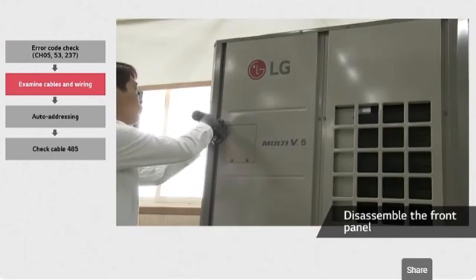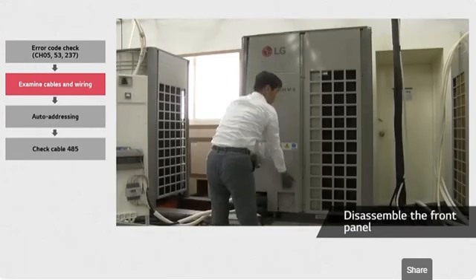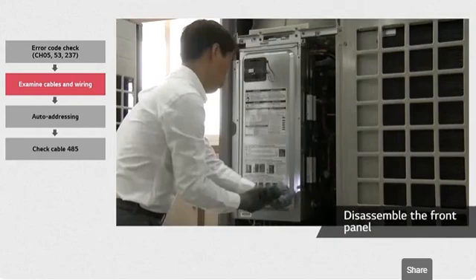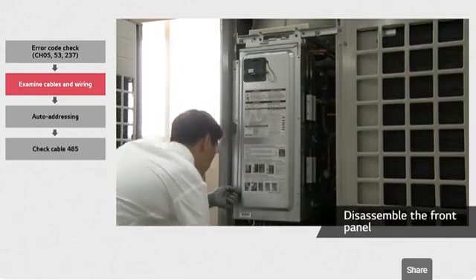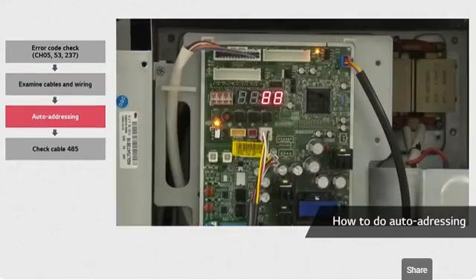To solve these errors, start by removing the front panel from the outdoor unit, and then disassemble the outdoor unit's control box. If indoor unit's main PCB is replaced with optional PCB, auto-addressing is needed. To do auto-addressing, press the red button on the outdoor unit's main PCB for 5 seconds, and the auto-addressing will begin when the number 88 comes on the screen. It takes from 2 to 7 minutes until the setting is completely done.